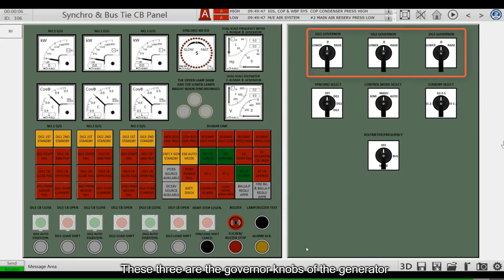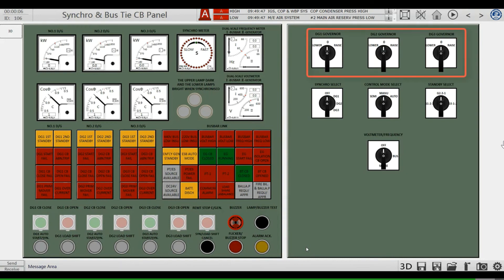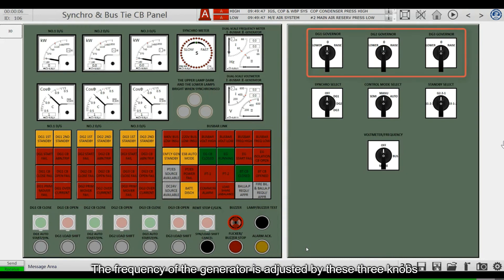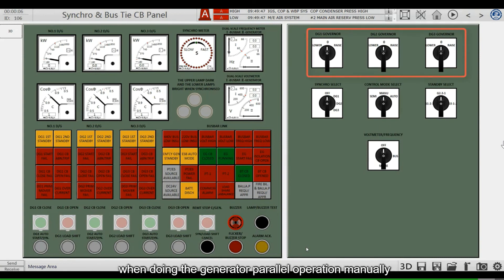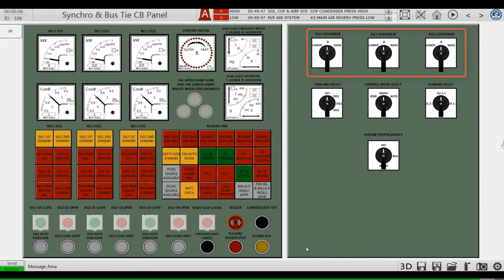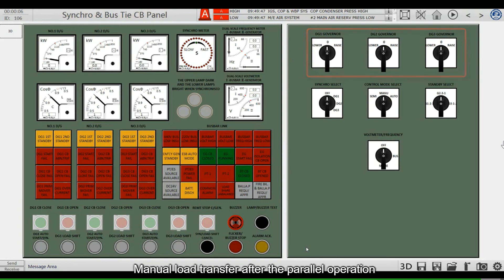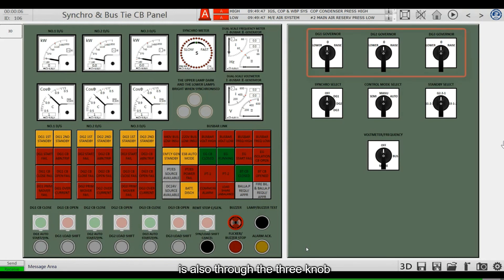These three are the governor knobs of the generator. The frequency of the generator is adjusted by these three knobs when doing manual parallel operation. Manual load transfer after parallel operation is also done through these three knobs.